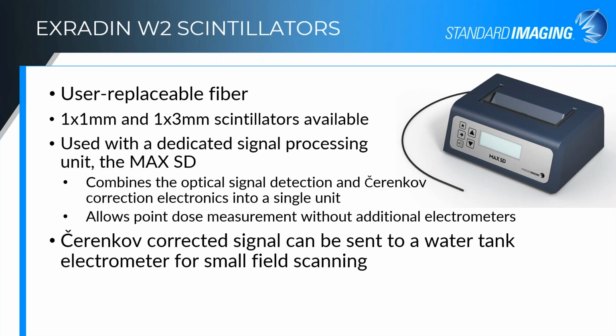We have then both the 1 by 1 millimeter option and the 1 by 3 available. The reason we were able to go down to the 1 by 1 with this was an advantage of combining the optics and the electronics, along with some improvements that we made to the optics, gave us a better signal to noise ratio, which then allowed us to be able to measure signal from that smaller detector. You can do your characterization measurements for the Cherenkov subtraction right with the Max SD. It has a web-based interface. You can also do point measurements directly with this device.